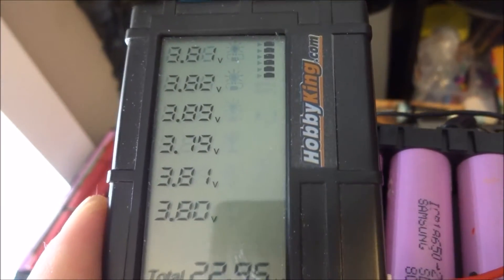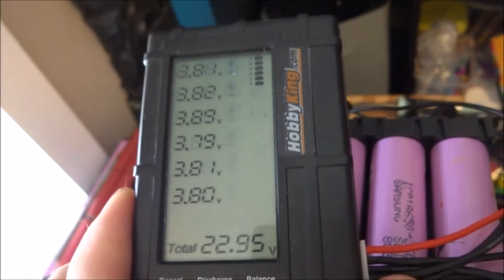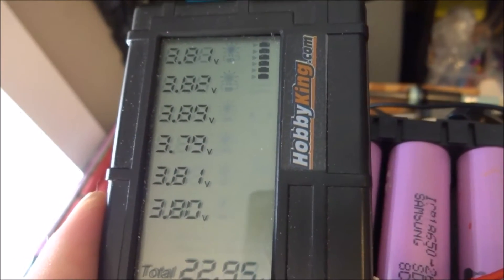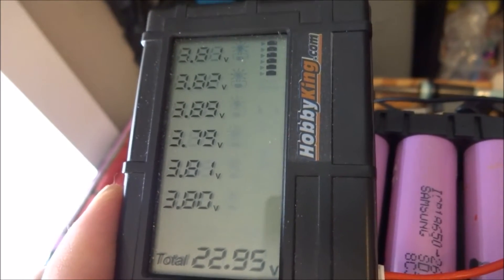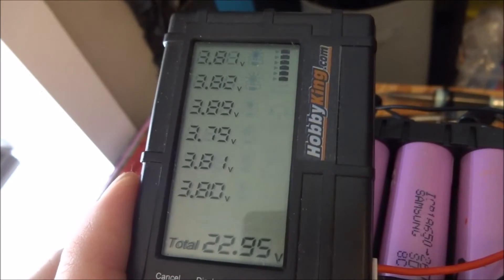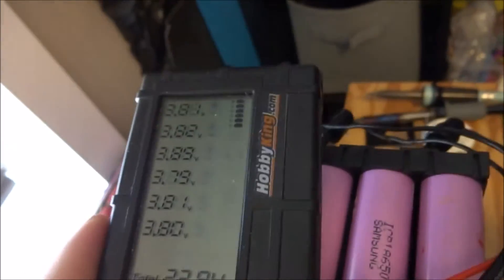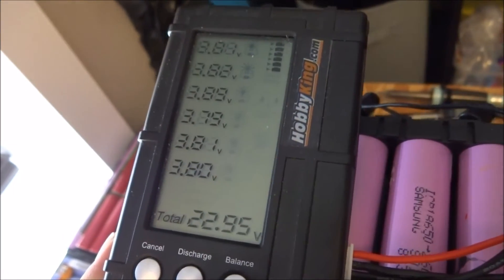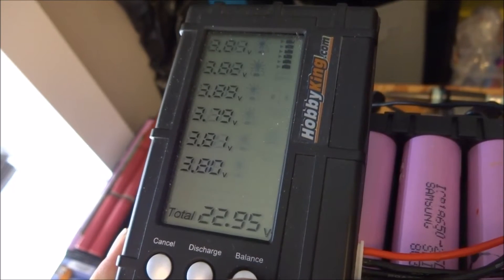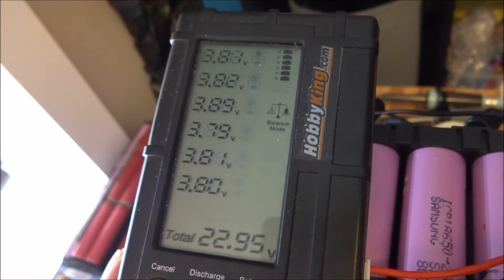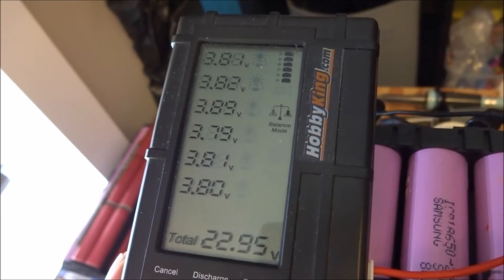Its storage mode was a bit higher than what I wanted, so now the ones are at 3.8. So there's a balance function here. If I hit balance, nothing's going to happen because I set the required voltage at 3.9. So they all have to be above 3.9 before it starts balancing.